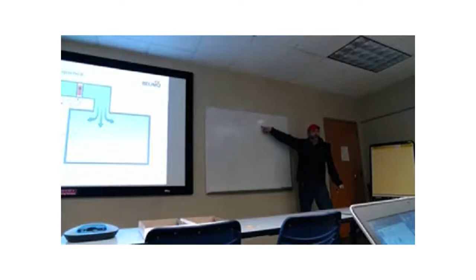All right, so back to the loop. The controller does all the magic in here. And then what it does, it outputs what I call a command signal. So that command signal, it could be in the form of a two-position signal, like a relay closure. It could be a 2 to 10 volt signal or some sort of analog signal. It puts it onto an actuator. This actuator is on what we call a final control element. And that final control element could be a damper, like an actual damper, or it could be a valve. Okay? So this is a loop, right?